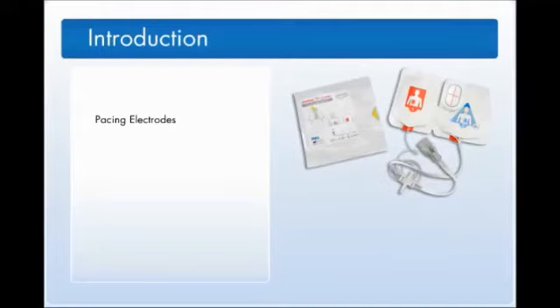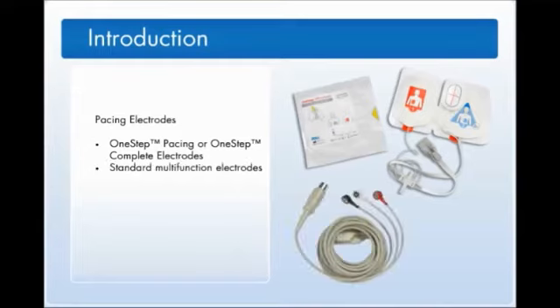You can use the R-Series to deliver non-invasive temporary pacing using the one-step pacing or one-step complete resuscitation electrodes, or you can use standard multifunction electrodes and a separate ECG cable. For pacing, one-step pacing or one-step complete electrodes need to be placed in the anterior-posterior position. When you use standard multifunction electrodes, apply them before you apply the ECG electrodes.